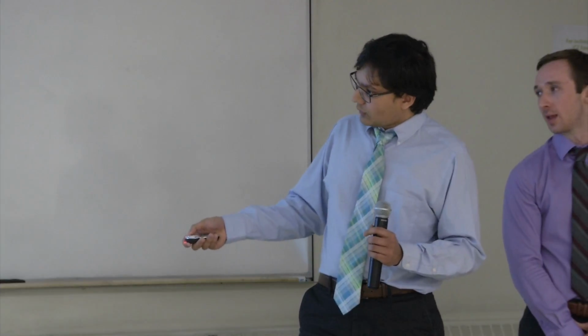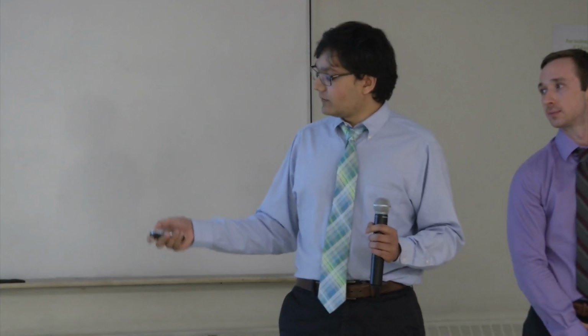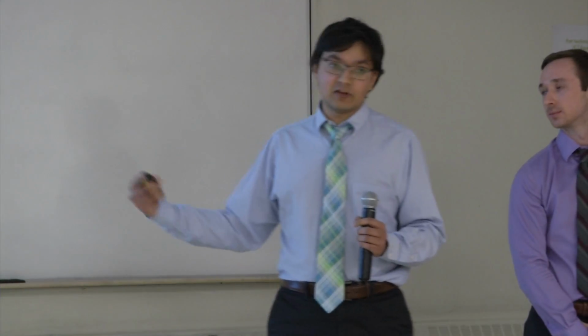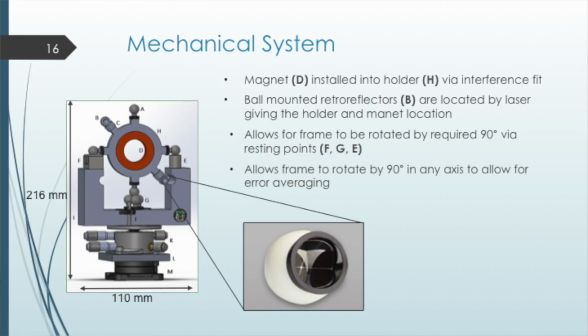Now, in order to position the holder, we have to use what are called ball-mounted retroreflectors. This works by simply firing the laser into the retroreflector, which then uses a series of mirrors to reflect the laser back to a detector, which can then figure out exactly where they are specifically in three-dimensional space, and thus figure out where the magnet is.